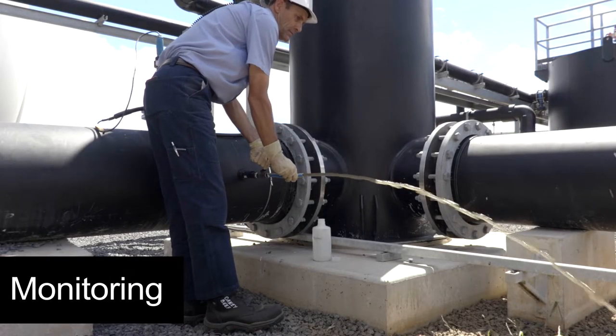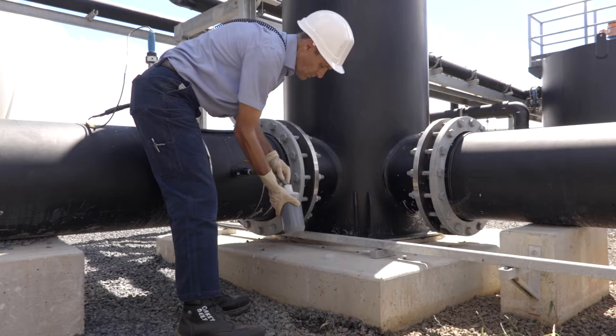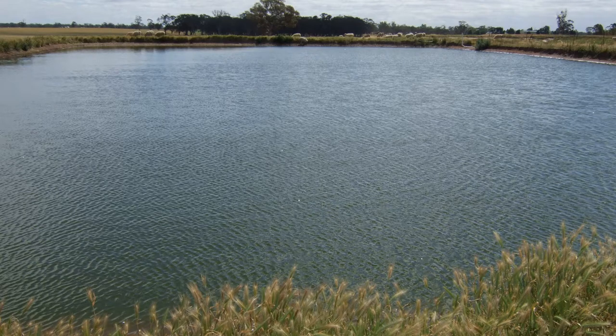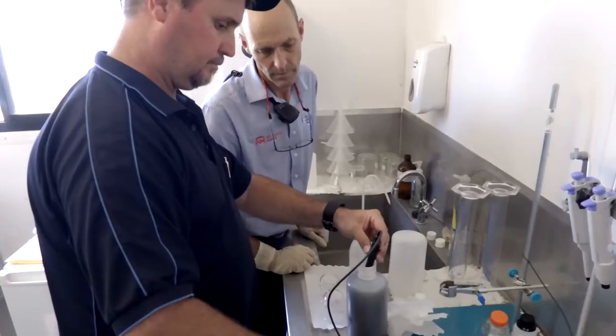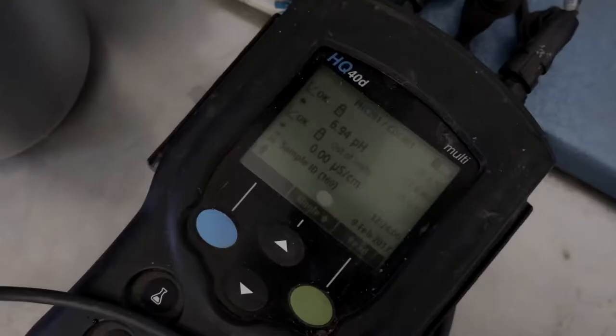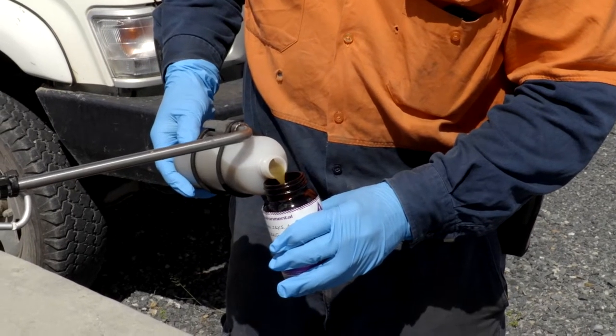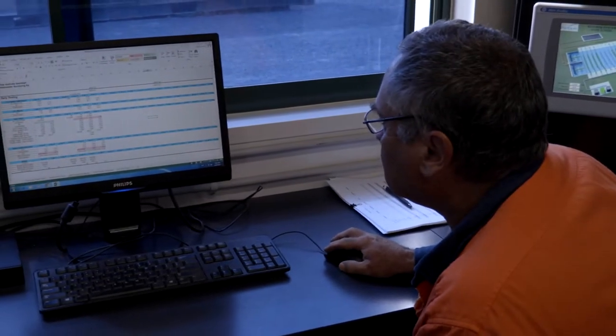Outlet sampling and testing of anaerobic ponds on a regular basis is recommended. If intensive treatment systems follow the anaerobic pond downstream, such as activated sludge systems or discharge to sewer, this sampling should be conducted as often as weekly. If the treated water flows to facultative ponds or is disposed to land, the frequency may be relaxed to once each month or quarterly. AMPC's Wastewater Management Manual provides details on critical parameters and preferred ranges. I go to the covered lagoon inlet — by that time the sun's up — and I do two readings there: a temperature reading and a pH reading. I continue my circle around, checking for leaks and water on the cover. Then I do the outlet: temperature and pH. I just make sure we're getting enough flows out and check the level. Then I go back to the office and enter all that into the computer.